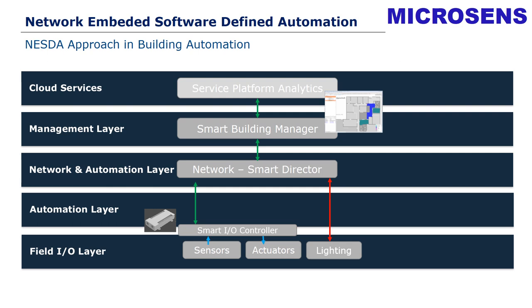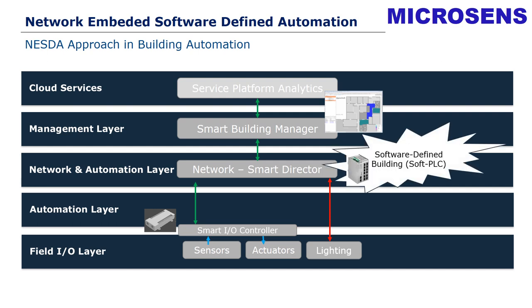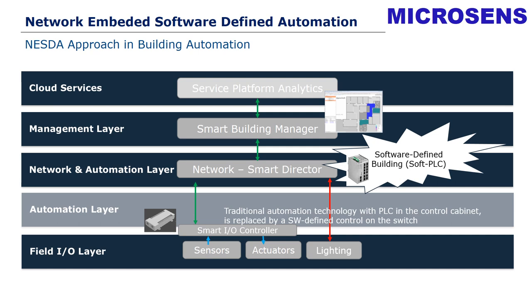What you can see here is that we jump over a layer — the automation layer. This automation layer, which was previously responsible for doing the automation, is in our case not really necessary, because we have implemented a software-defined PLC, or soft PLC, into the network layer, which covers all the tasks for automation that were previously installed in the cabinets of the automation layer. By doing this, the traditional automation technology with PLC in the control cabinet is replaced by software-defined control on the switch.